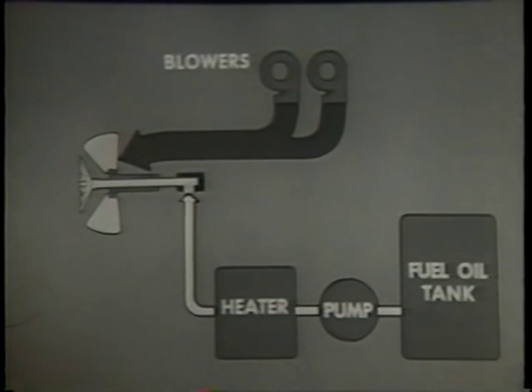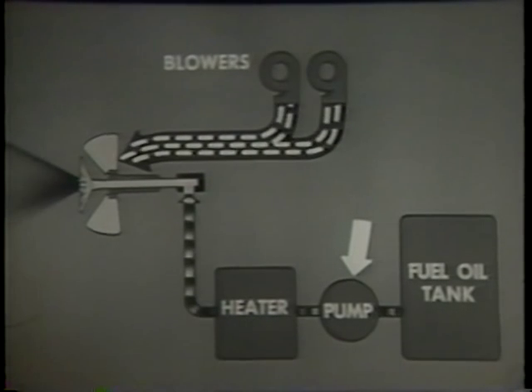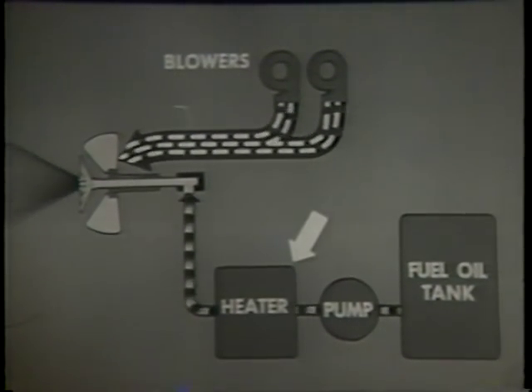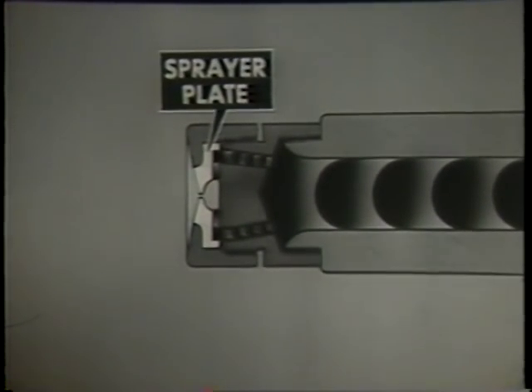The forced draft blowers send a strong blast of air to the burner. The fuel oil pump sends the oil through the heater where the oil is heated to give it good flow quality, then the oil is pumped to the burner. This simplified cutaway of the burner shows how the fuel oil is forced through the burner barrel to the atomizer nozzle, where a series of passages guide the oil to the sprayer plate. The sprayer plate makes the oil rotate at high speed, breaking up the oil into particles, and the oil leaves the atomizer as a hollow, mist-like cone or spray.